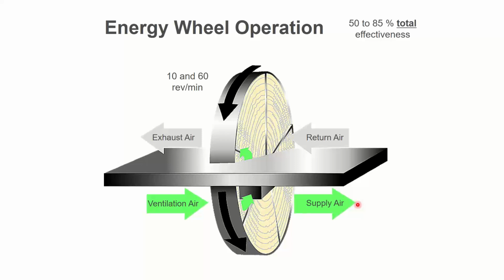It's going directly into the space, right? I shouldn't say that way, but if I don't have 100% outside air and I have return air from my system that goes back into my evaporator coil, what about that air, right? So it doesn't matter if the ERV is leaking a couple tenths of a percent. If the main duct system is allowing 70% of the return air to go back into the supply anyway, right?